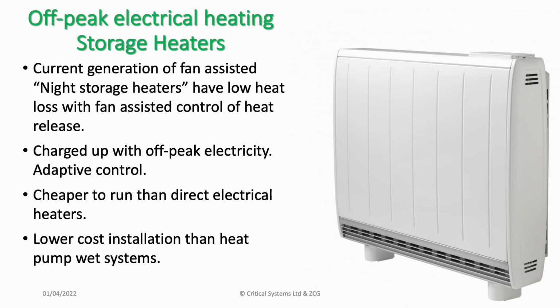Off-peak. So there are new generations of fan-assisted night storage or off-peak heaters. And these have very low heat loss during periods of no demand. They're charged up with off-peak electricity, usually Economy 7 type tariff. Can have adaptive control for charging and discharge. Cheaper to run than direct electrical heaters because they use off-peak energy. And they have a lower capital cost than heat pump wet systems.